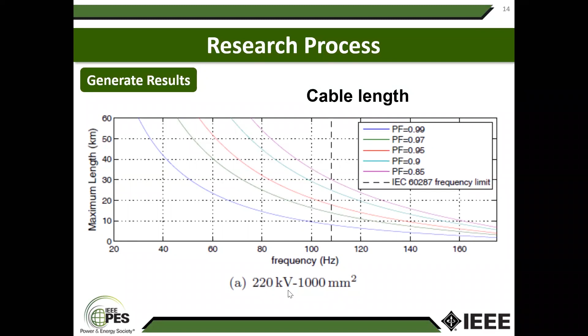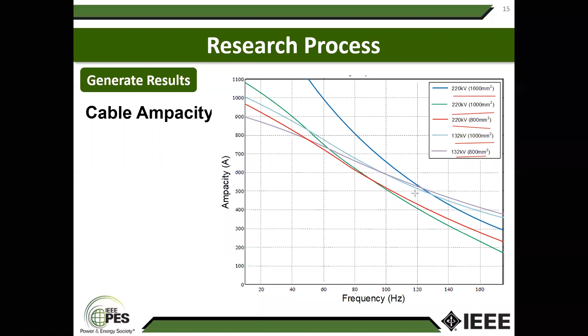Here we are considering 220 kV, 1000 millimeter square cables. Once you work out the frequency range, you can work out the cable ampacity. You can see for different cables - 220 kV at 1600, 1000, and 800 millimeter square, and 132 kV at 1000 and 800 millimeter square - how the current carrying capacity varies with frequency.